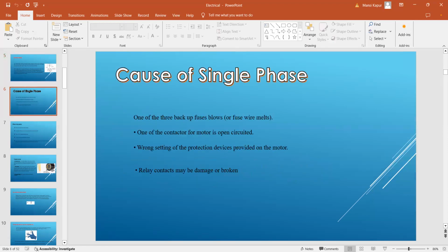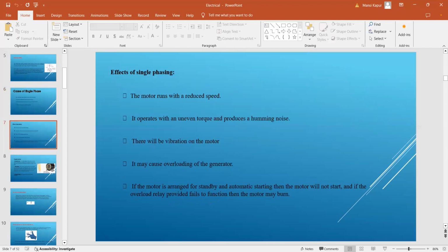Okay, so one of the contactors for the motor is open circuit, or one of the fuses is blown. In all three phases, we have one fuse, right? So suppose the motor was running and this fuse is blown. This is as good as single phasing, right? Or one of the contactors is open, or the wrong setting of the protection device on the motor. So suppose you have put the wrong value of the fuse, or a relay contact is broken or damaged. These all can lead to single phasing. So next, what will be the effect of single phasing?